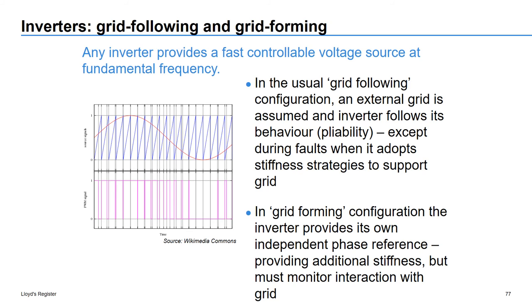What's called the grid following configuration is by far the most common and widely used. It works on the principle that an external grid is present and it should simply follow the voltage in that external grid when determining the appropriate current and the appropriate power to inject into the system.